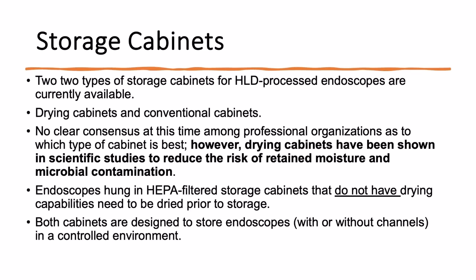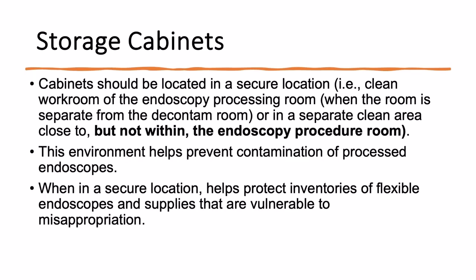Understand that a conventional storage cabinet will have the filtered air around the outside of the scope, but does not dry the channels. A drying cabinet will dry the channels. Both cabinets are designed to store endoscopes with or without channels in a controlled environment. Cabinets should be located in a secure location. It could be in the clean work room, but it cannot be in the procedure room, and it cannot be in a decontam room. This environment helps prevent contamination of processed scopes.